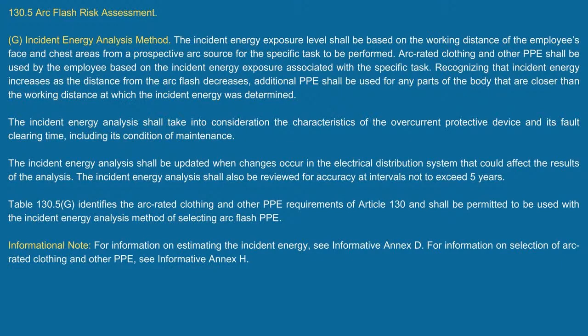Now, I want to drop down to the second part here. It talks about the incident energy analysis, and look what it says. It shall take into consideration the characteristics of the overcurrent device, and look at this, its fault clearing time and its condition of maintenance. Now, I'm going to tell you, even though I'm doing the calculation method here, you're still going to have to do that when you're using the table method. Okay, and we'll get into that.